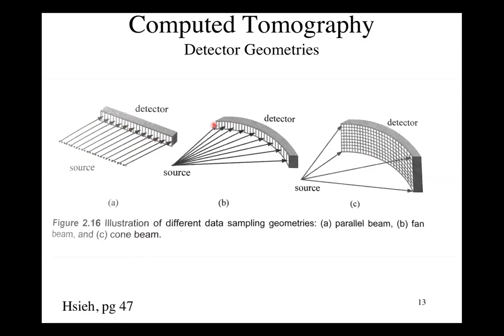Oftentimes, CT scans are inside a cylindrical tube, and so the detector is essentially an arc of a circle, and the source, instead of being parallel lines like this, which you have to raster across and is hard to engineer, is a single source. We can get these different projections through the object from a single source all at once. So this speeds up the whole process. Obviously, I can just do a flash and I get all of these at once. Whereas with this, I would have to raster across and get each projection one at a time.